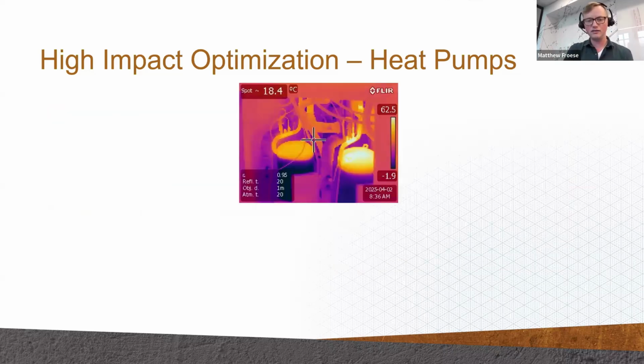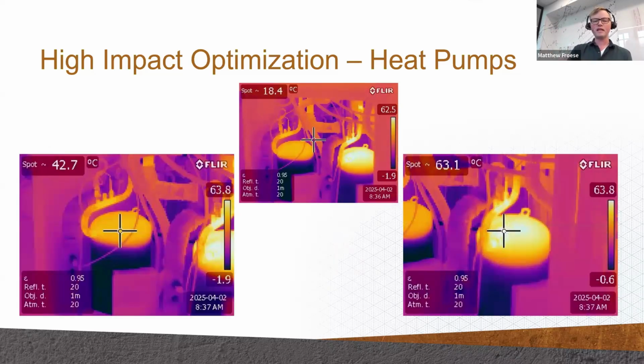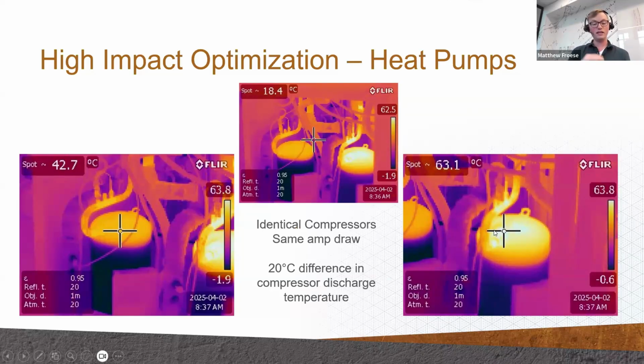And this is an infrared shot of those two compressors, the same things. The only thing you need to know about them is when they're working, the bottom is cold and the top is hot. That's what the compressor is doing. It's moving heat, and the brighter colors there are hotter. So what we found here is the difference between that first compressor and the second compressor is that when they were both running, they would draw the same number of amps because they're both running, but the compressor on the right was the only one actually doing any work. The leaving refrigerant temperature was 20 degrees Celsius higher, and it was the only part of the unit that was really working.